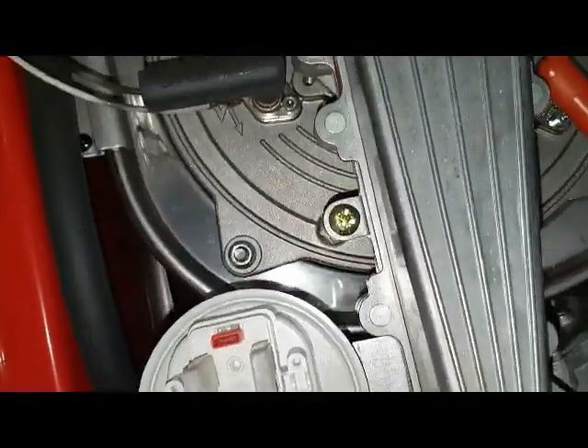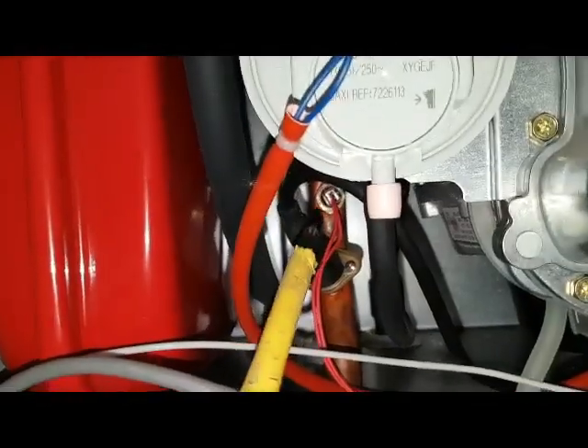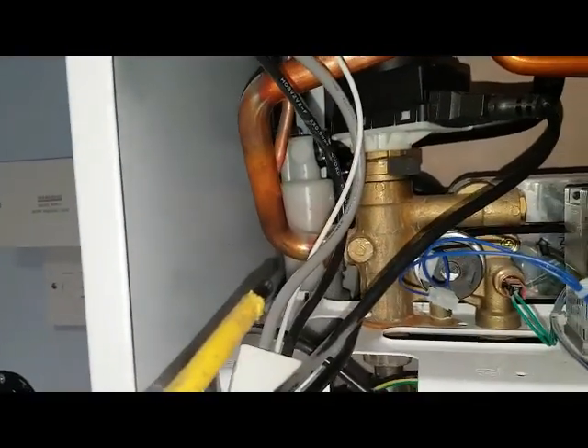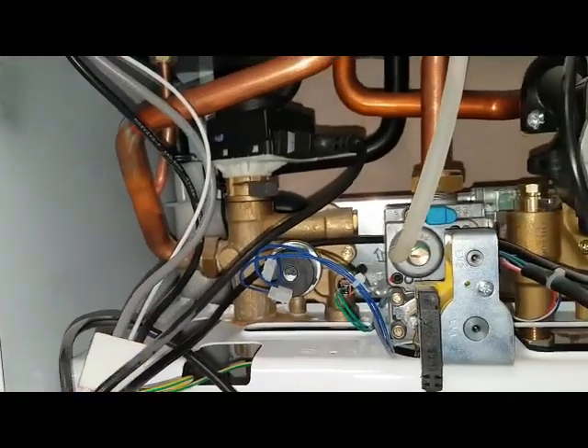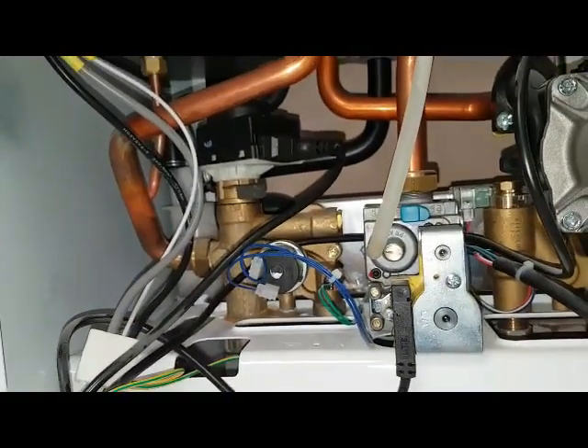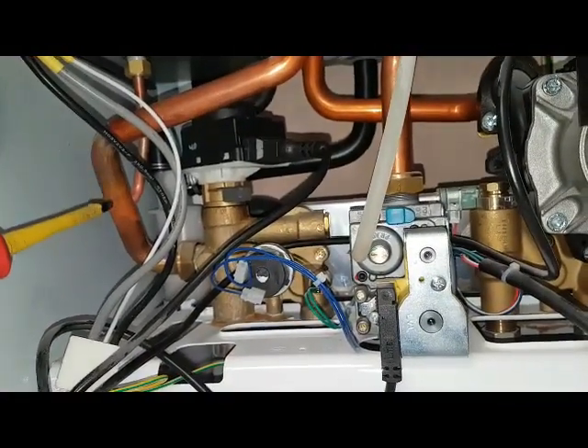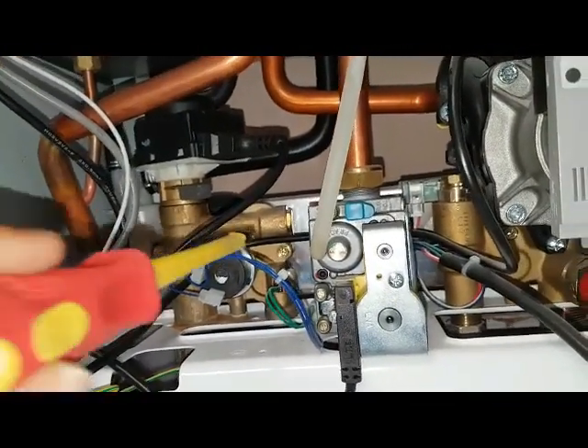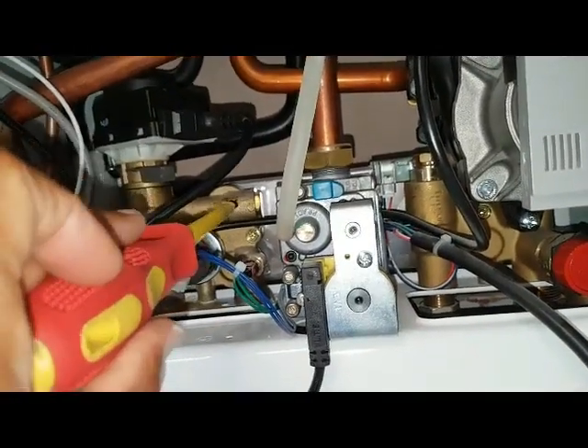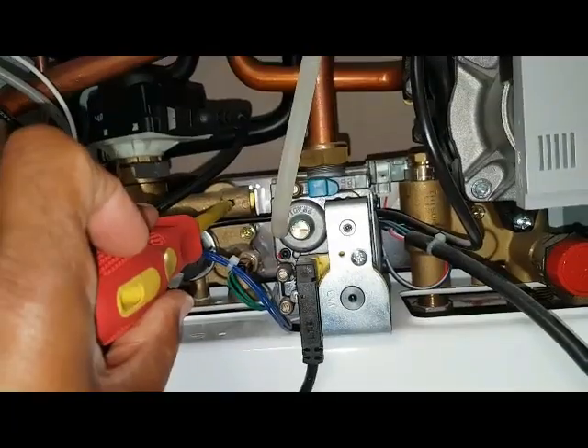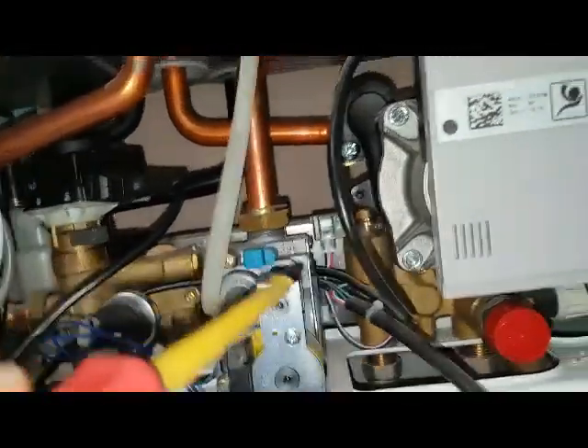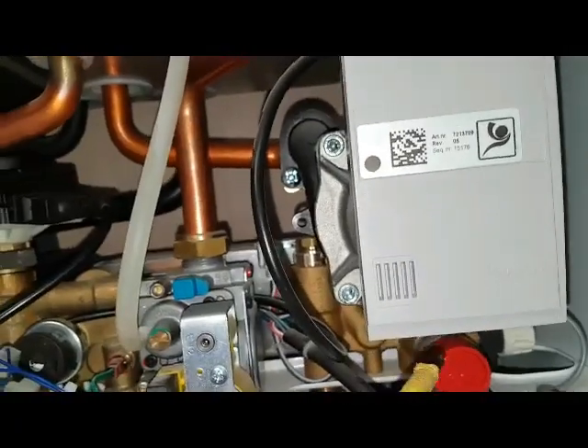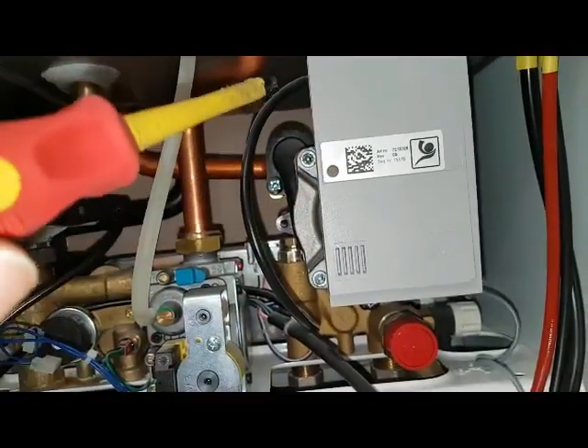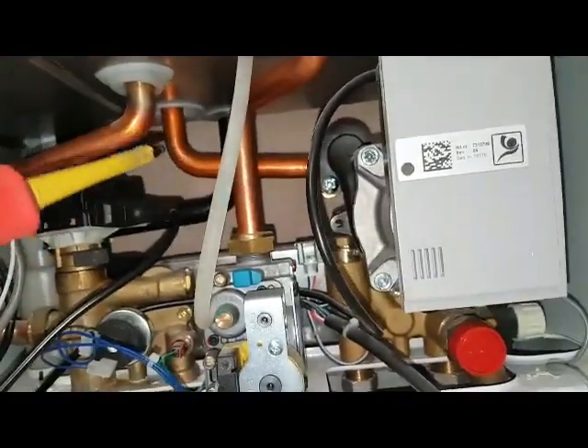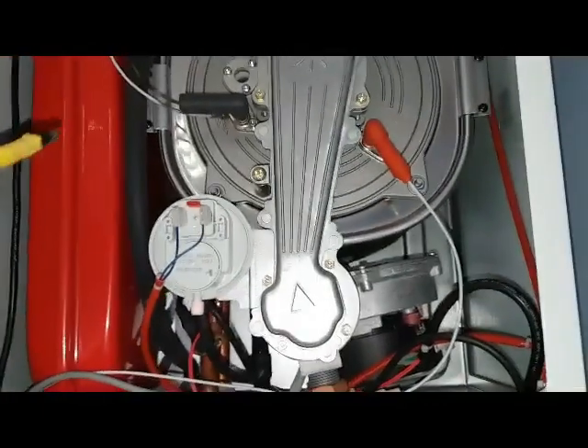The primary water is getting hot through that flow pipe, going down into the divert valve. Because the divert valve is in the right position, it shuts the port off to the heating. That hot primary water goes through there and then into the plate. Then that primary water turns the cold water into hot water. It goes through the plate, out the other side, through the pump. That's returning back up through that pipe there, up into the main heat exchanger to get heated.